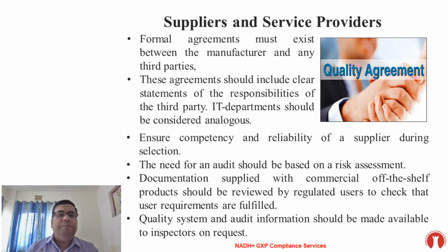the basic requirement is that a formal agreement must exist between the manufacturer and third parties. This agreement should include clear statements of the responsibilities of the third party. The IT department should be considered as analogous. Ensure competency and reliability of a supplier during selection. The need for an audit should be based on risk assessment.